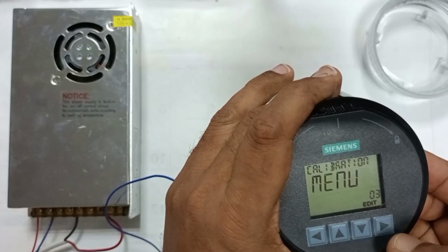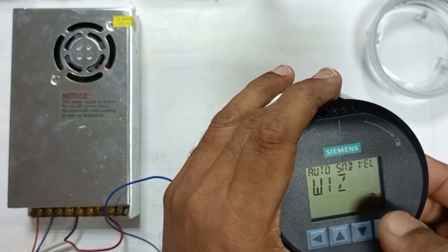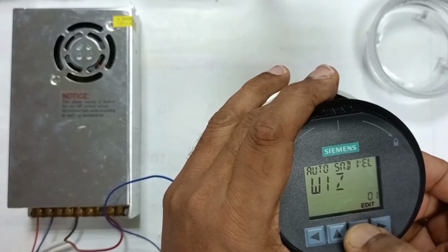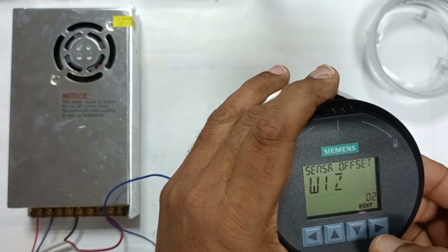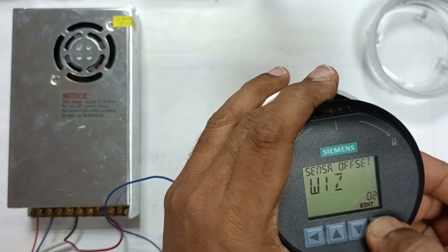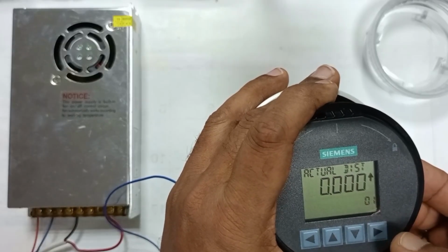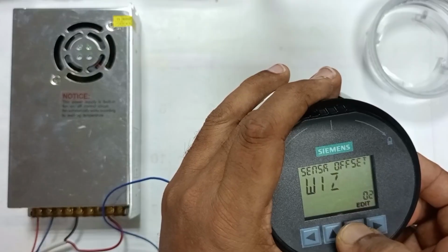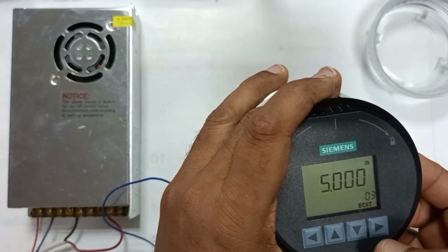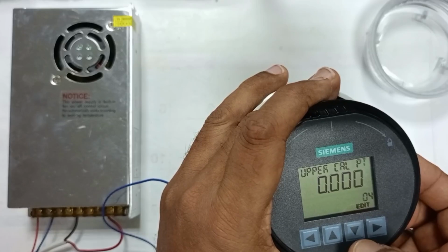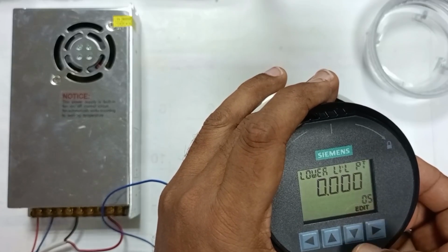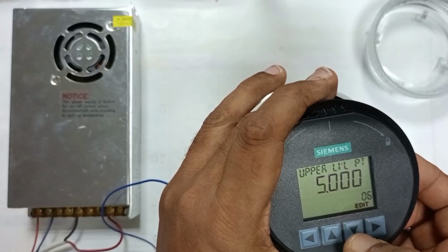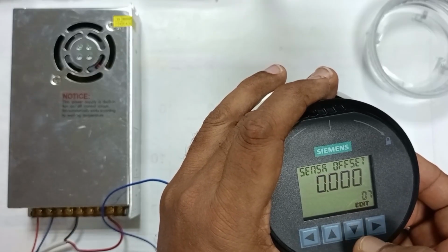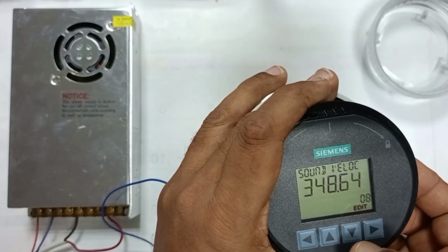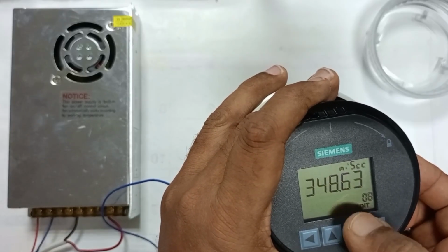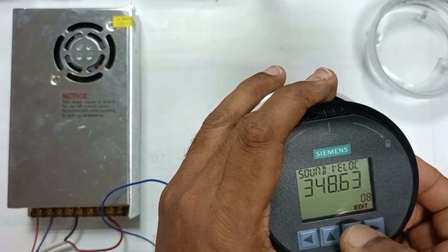Okay, this is very important and we'll calibrate now. Here auto, and sensor offset value. You can change this, or you can increase or decrease this value. The lower calibration point is 0 and the upper calibration point is 5. Sensor offset 0, and sound velocity in meters per second. This is sound velocity. It can be changed or there is no need to change.